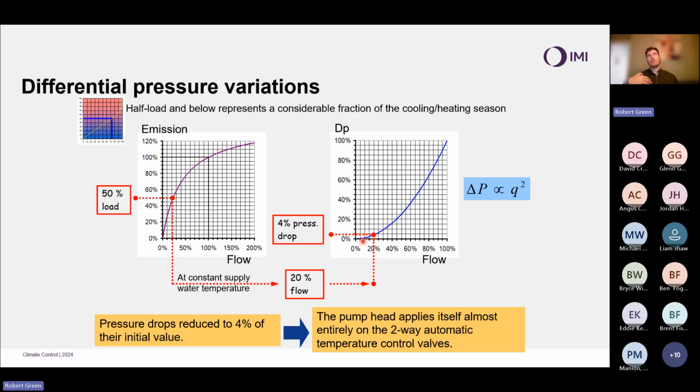And in the session we will have in 2 weeks' time or so, we'll look at how that affects a control valve. But it's something to bear in mind from a dynamic perspective. We looked at dynamic balancing in the last session, and this is something really important as to why dynamic balancing is there. It's because of these huge variations in differential pressure during the operational time of a system.